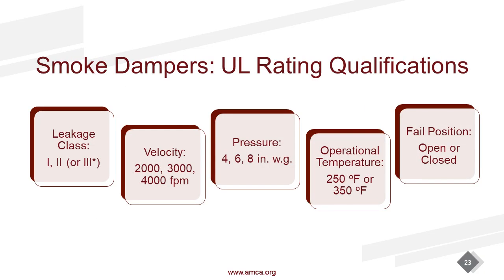So just like we had a Carfax on fire dampers, we have them on smoke dampers. They go through the UL 555S standard. And we need to know, what is the leakage class? Leakage is the amount of air that will pass through the damper when the blades are in the closed position, and that air will carry smoke. So that is, of course, one of the most important things we need to know.